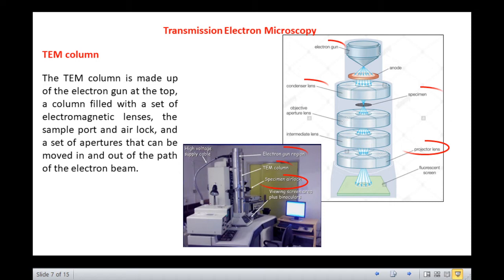The entire contents of the TEM column are under vacuum as electrons have insufficient energy to pass through gas and water molecules. This vacuum is achieved by oil diffusion pumps backed up by rotary pumps.